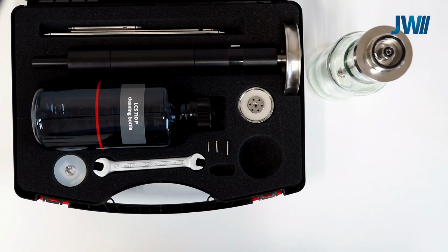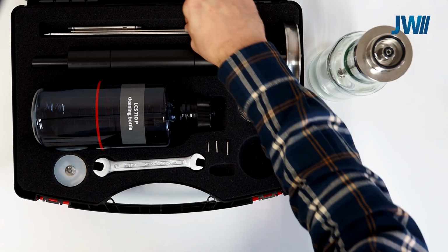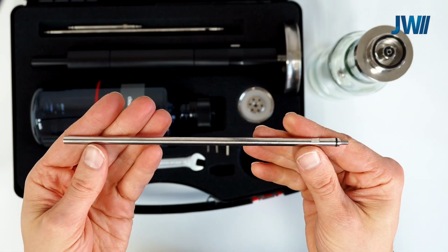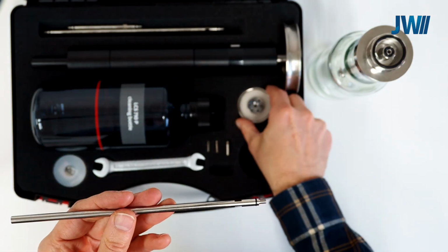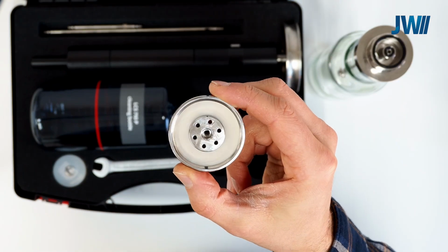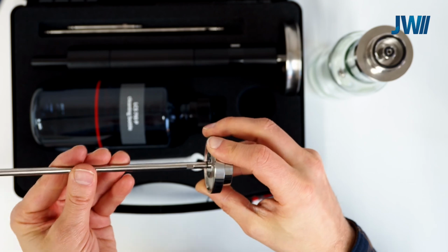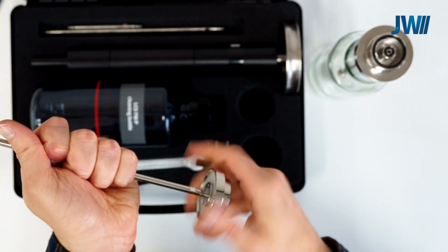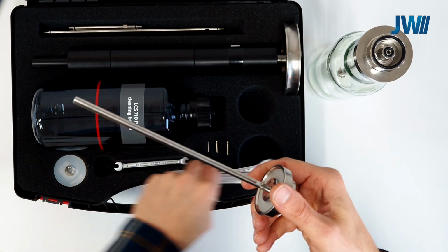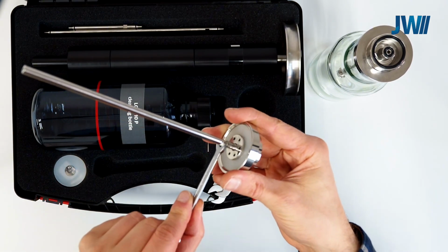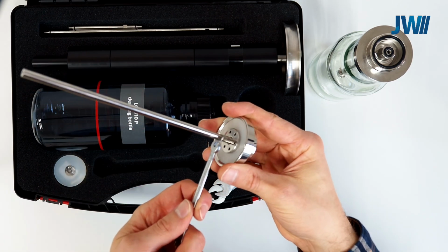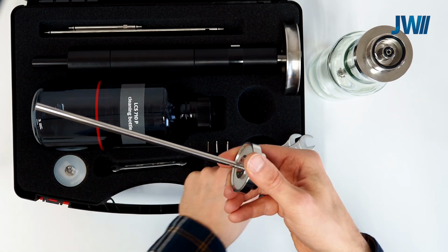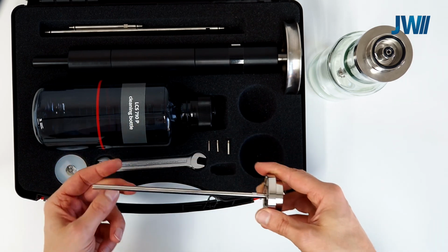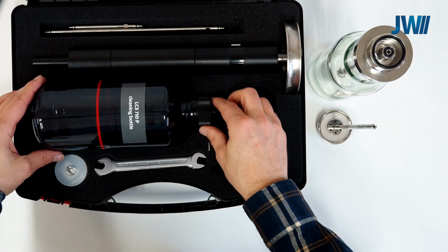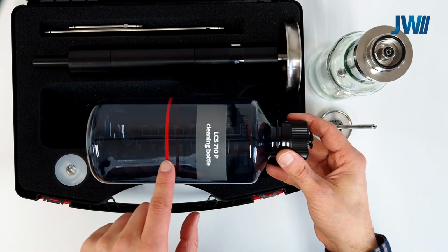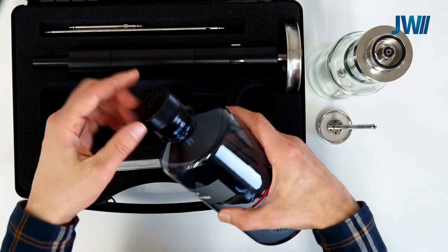For cleaning, we need to prepare the cleaning probe. Use the tube that has a thread on only one side. The cleaning head is the smaller one with many holes. If screwing by hand doesn't work well, you can use wrenches for assistance. Do not over-tighten, as this may damage the threads. This is the cleaning bottle. Fill it to the red line. You can use hot water or alcohol for disinfection.